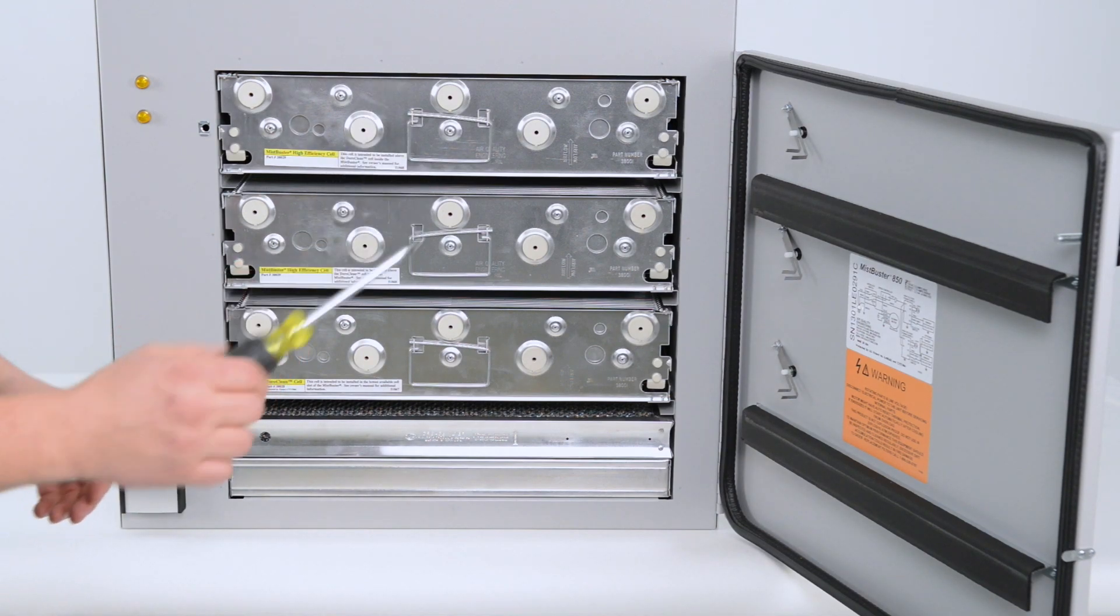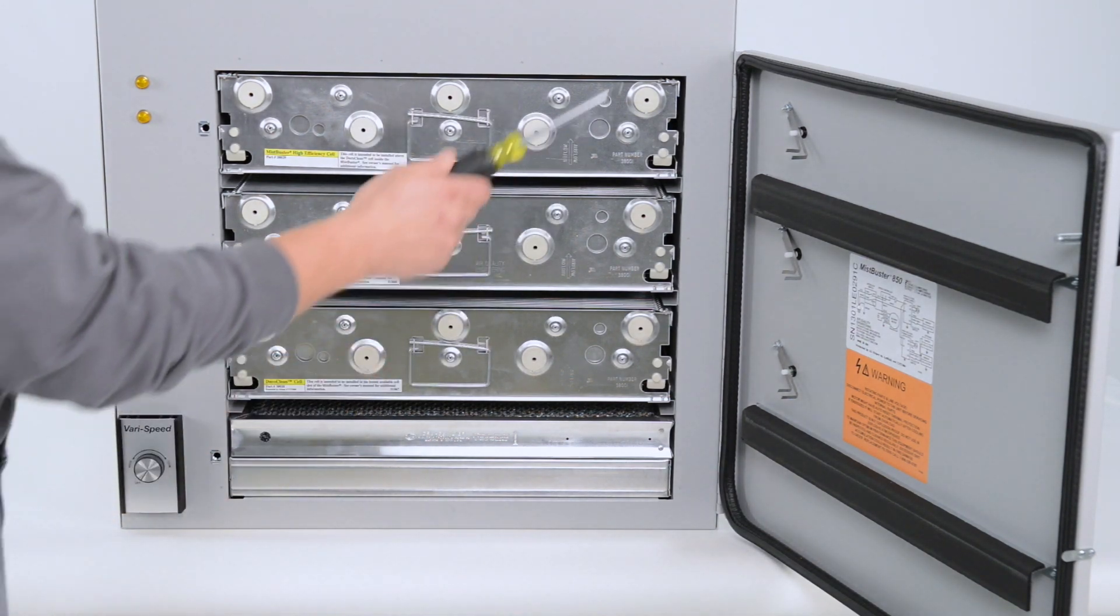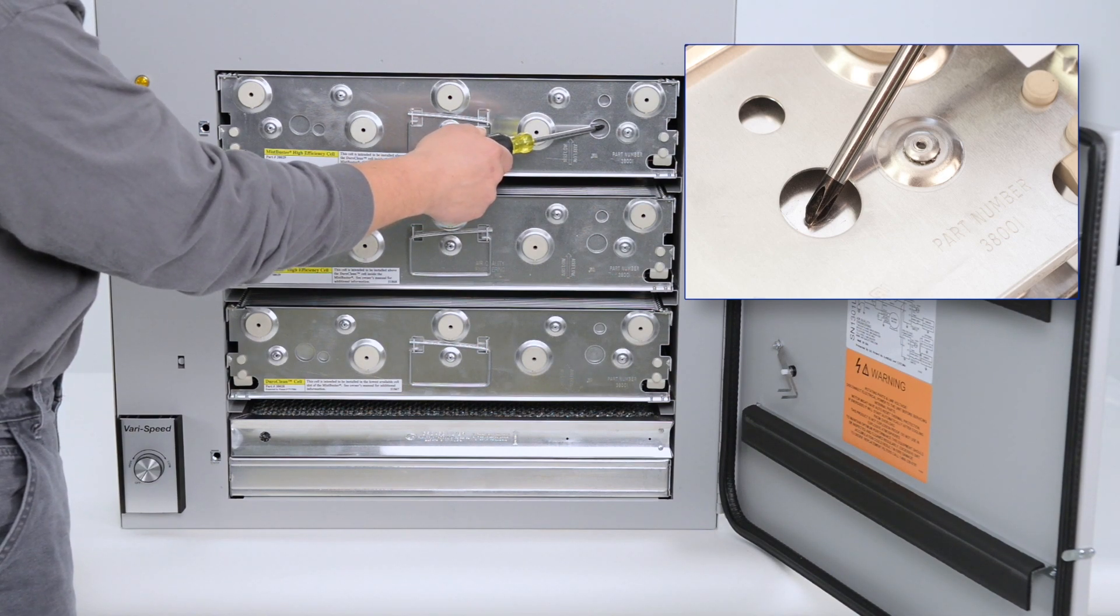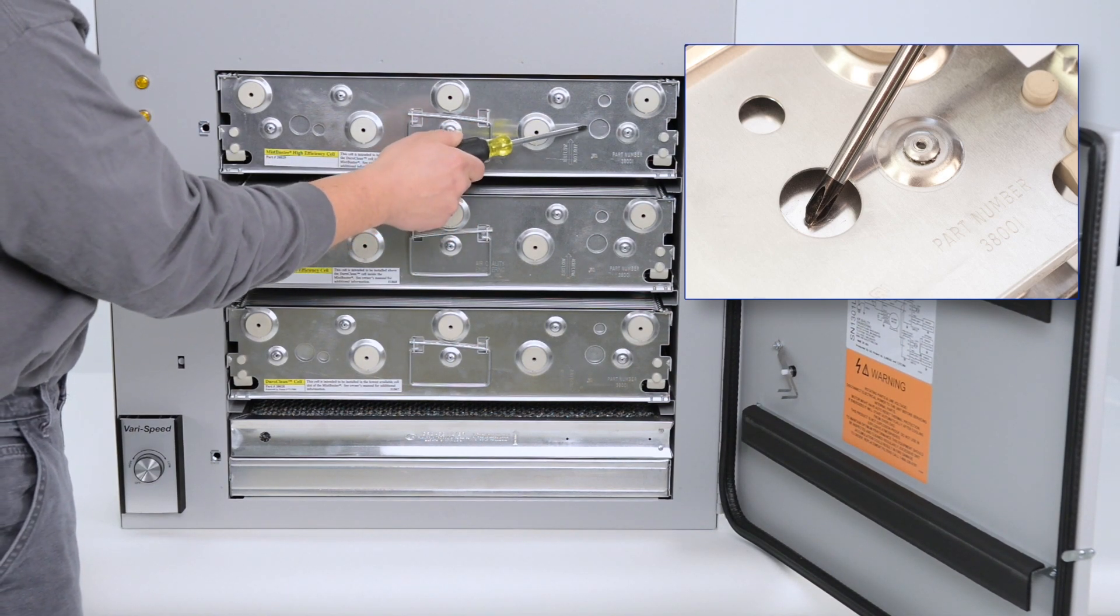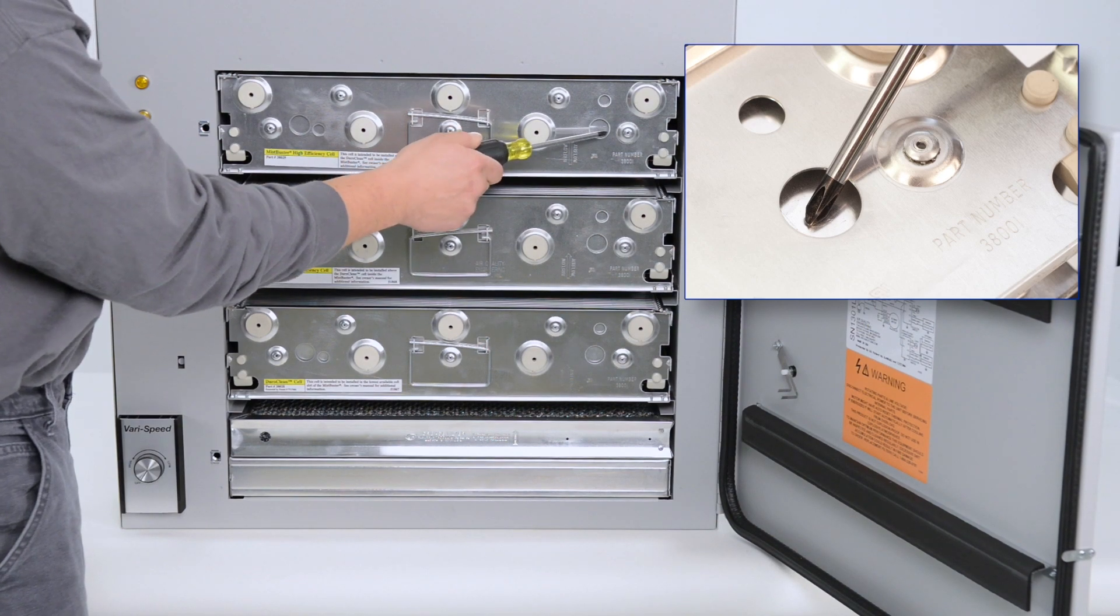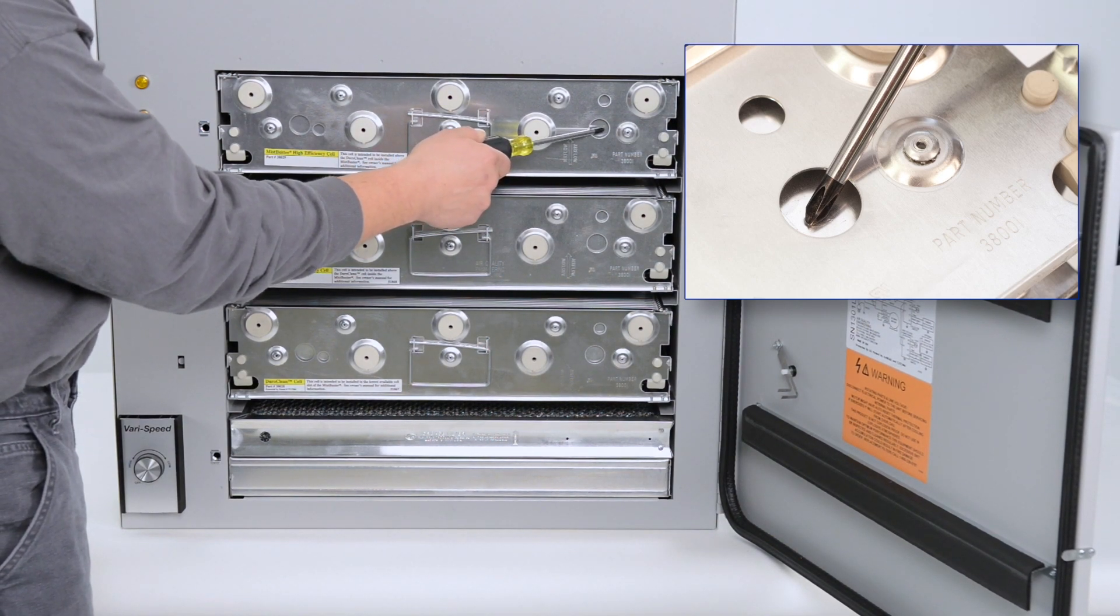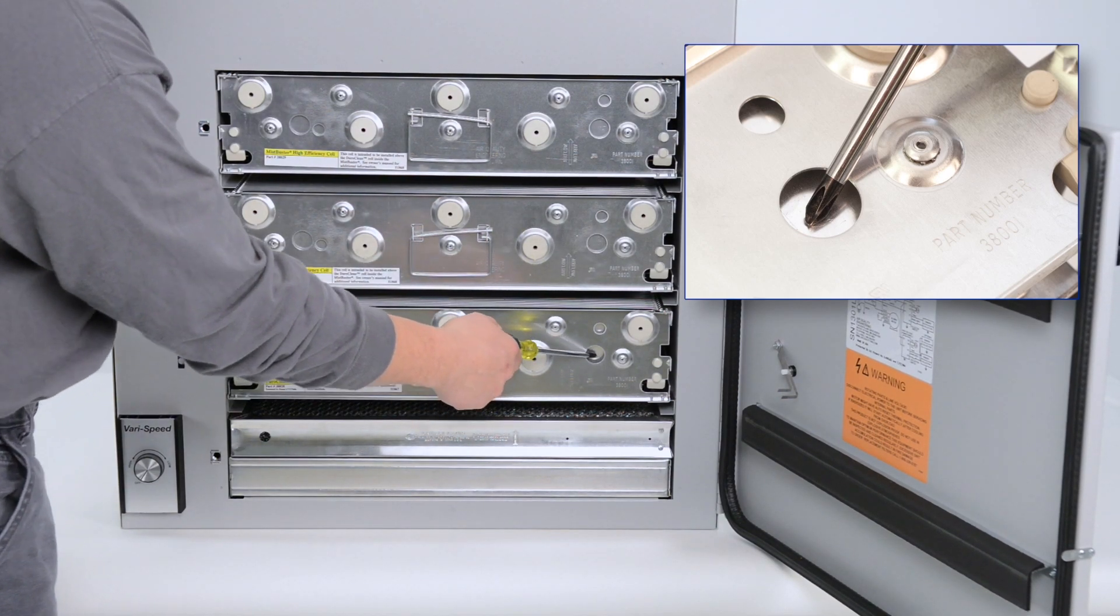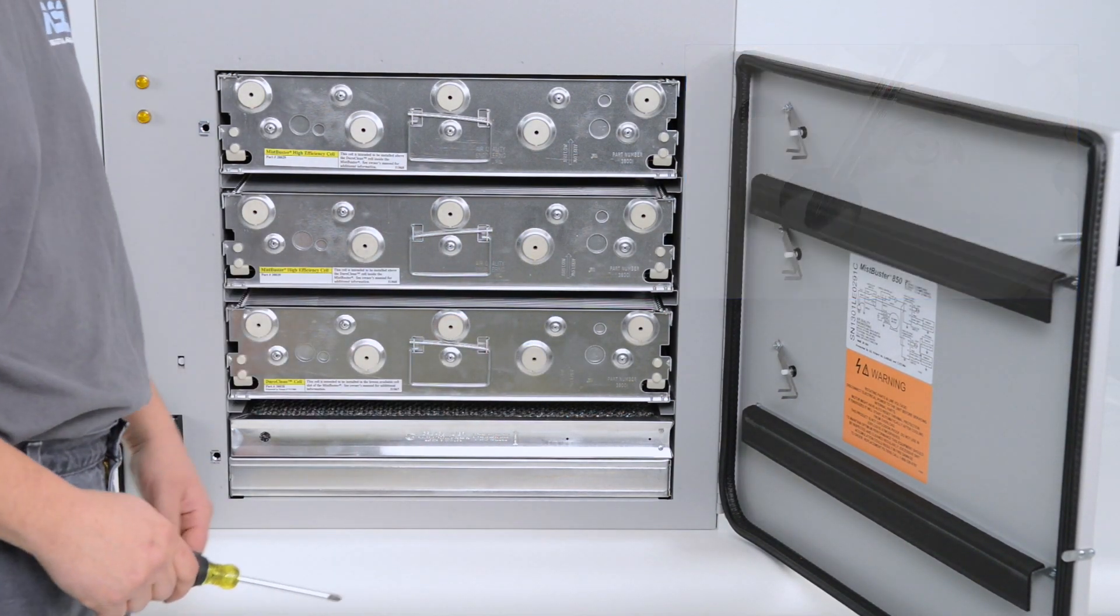Next, using an insulated screwdriver, touch the tip of the screwdriver to the base of the collection cell and also touch the first collection plate. This is a safety measure just to ensure that the cells are actually grounded before you touch them.